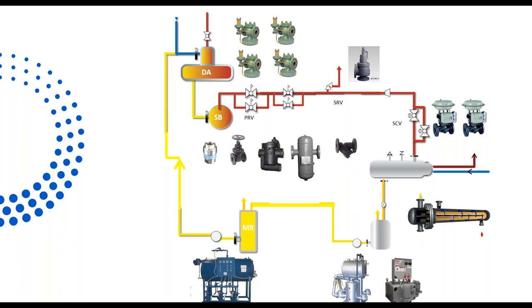So this is a typical conventional steam design that we've been using for more than 100 years. What has changed over time is the color of the valves or the pumps and things like that. So typically you need a 1/3, 2/3 pressure reducing valve. You come out with high pressure steam from the boiler, bring the high pressure steam into every building in the campus, and then you reduce the pressure.